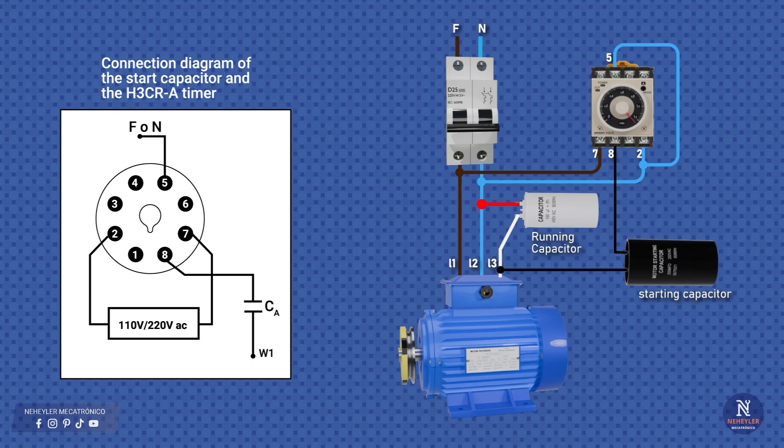Before turning on the motor, it is important to adjust the disconnection time on the timer. This must be between 3 and 5 seconds, depending on the motor power. In this way, when turning on the motor by switching the circuit breaker, the NC contact of the timer is closed and the start capacitor enters service. Then, after the configured time, the timer opens the contact and disconnects the start capacitor, leaving only the run capacitor in operation to maintain motor rotation.